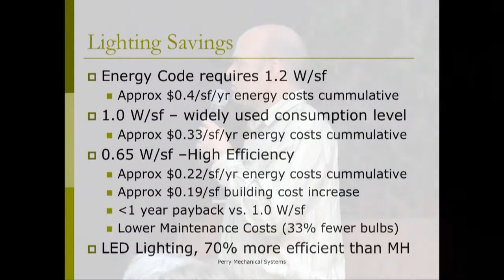So this is a little messy, but it's an overview of lighting savings here. If you look at what the energy code requires on a watts per square foot basis, you're going to be at about 1.2 watts per square foot. That translates into about 0.4 cents per square foot per year in energy consumption. A lot of the designs these days go a little bit beyond the 1.2, to about 1.0 watts per square foot. So I'm going to use that as a baseline.